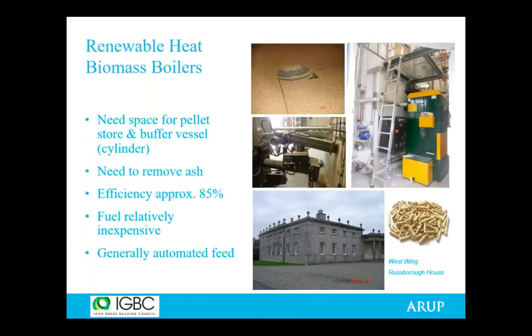Biomass boilers, or energy from biomass — you can use biomass to fuel a CHP, but generally we're seeing biomass being used just as a fuel for heating. You tend to need a lot of space for the pellet or wood chip stores. There's ash produced through the burning of the pellets that needs to be removed, so there's more maintenance, and the boilers are not as efficient as, say, high efficiency condensing boilers.